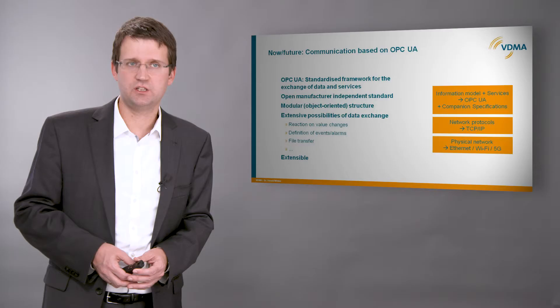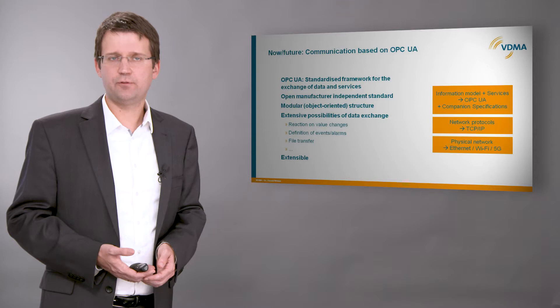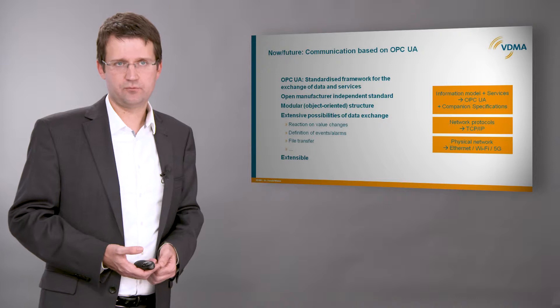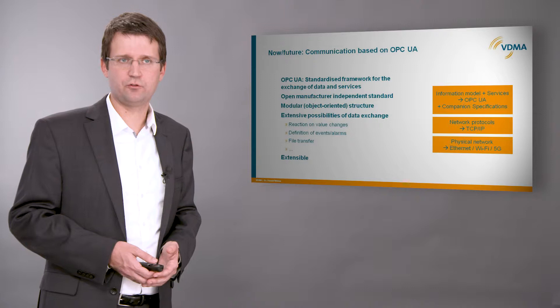This is why a group of manufacturers producing one kind of plastic processing machines, namely injection molding machines, started to create a new interface in 2014. They decided to use OPC UA as a basis. The main reason for this choice was that OPC UA is manufacturer-independent and offers a modular, object-oriented structure with many predefined functionalities. It just needs an IP-based network independent from the lower communication layer. But what is most important, OPC UA offers the mechanism of so-called companion specifications.